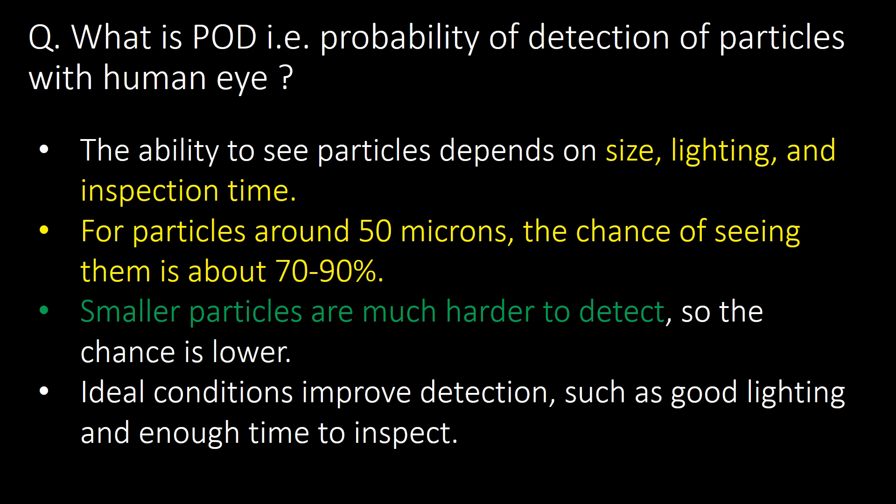What is POD — probability of detection — of particles with the human eye? The ability to see particles depends on size, lighting, and inspection time. For particles around 50 microns, the chance of detecting them is about 70 to 90 percent. Smaller particles are much harder to detect.